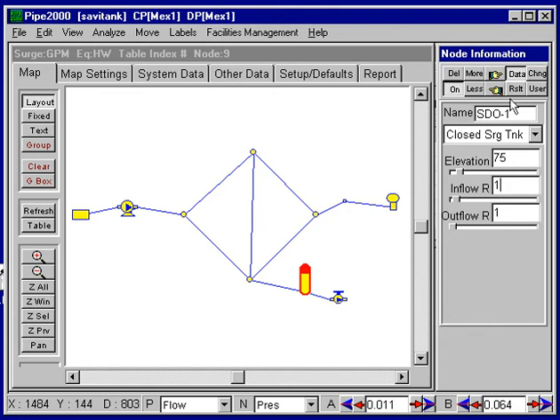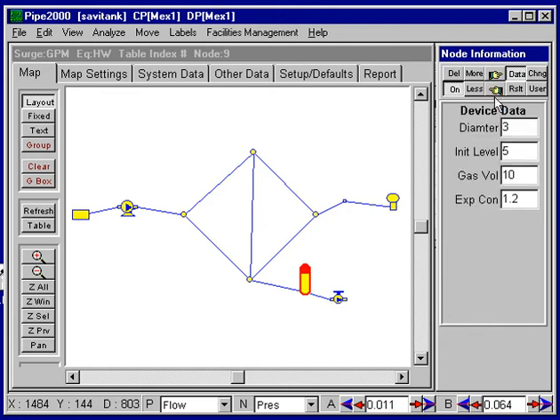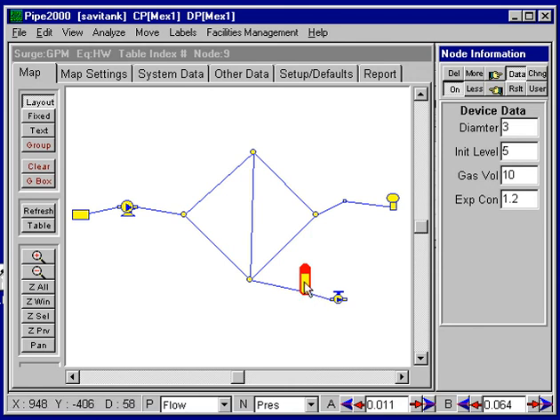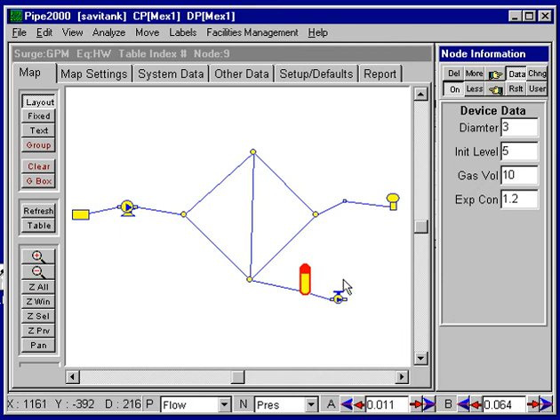We have some additional data here that we'll enter: a diameter of 3, an initial water level of 5, and a gas volume of 10 cubic feet. The gas expansion constant refers to the process of compression — whether it's isothermal, which would be 1, or adiabatic with no heat loss, which would be 1.4. We'll choose 1.2 because we don't know exactly what the process will be.